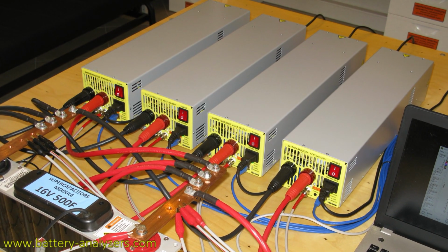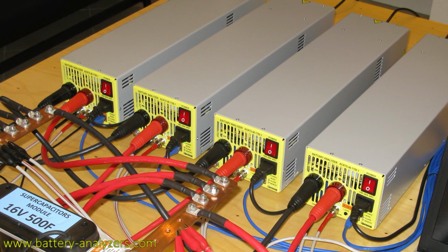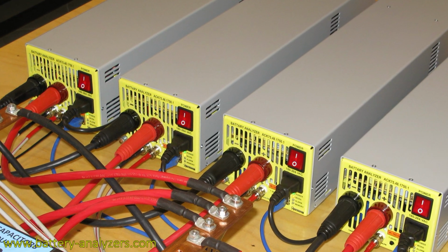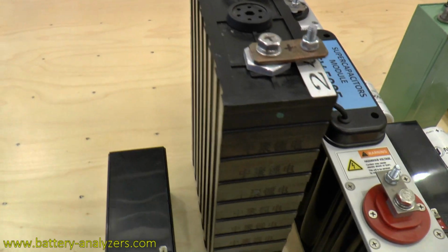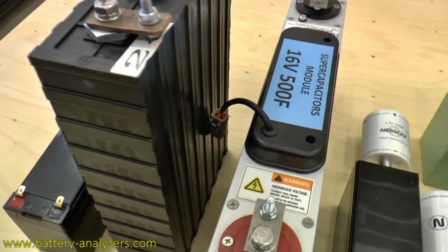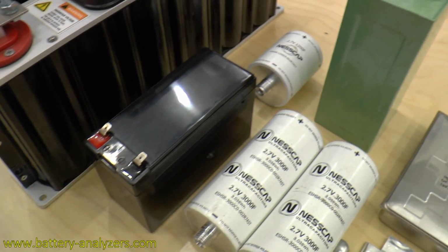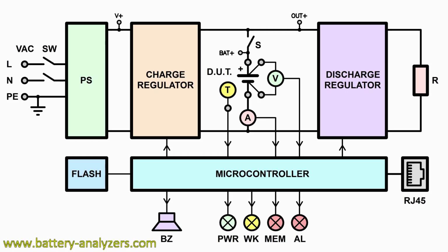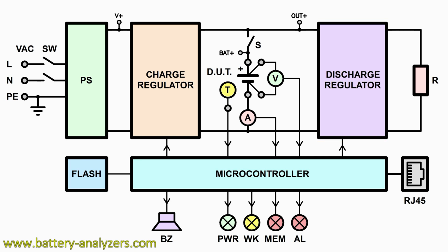Hello dear viewers, in this video we will get acquainted with analyzers of batteries using the example of the analyzer ACK100.24.650.1. The devices are designed for testing accumulators and storage batteries of any type, supercapacitors, supercapacitor modules, galvanic cells, fuel cells, Redox batteries and any other sources and storage of energy. The analyzers combine a programmable power supply and a programmable electronic load, and are available in various modifications.